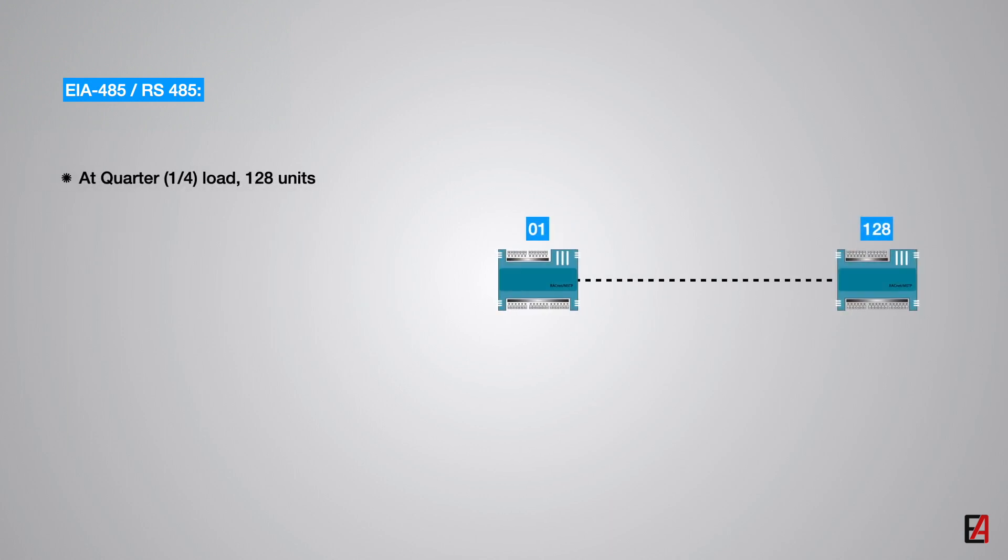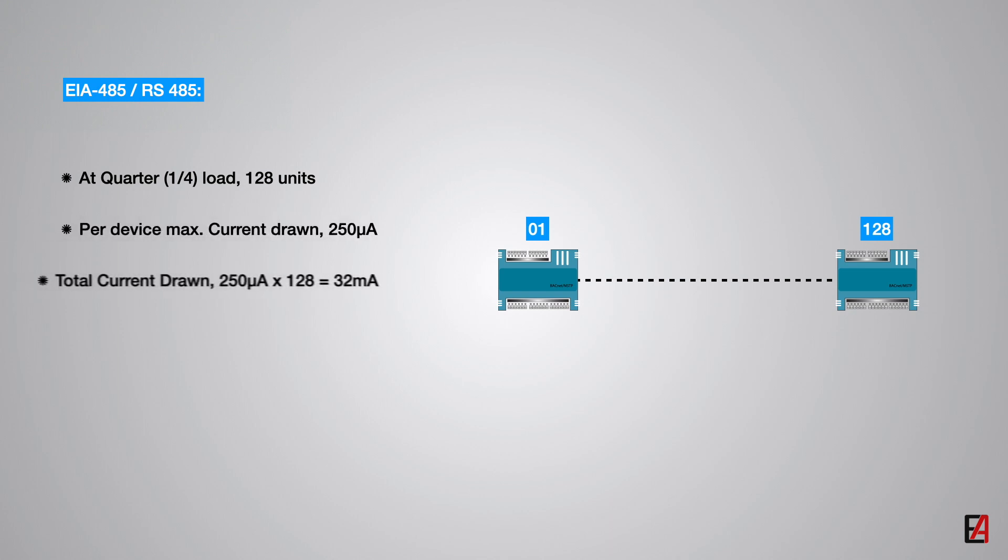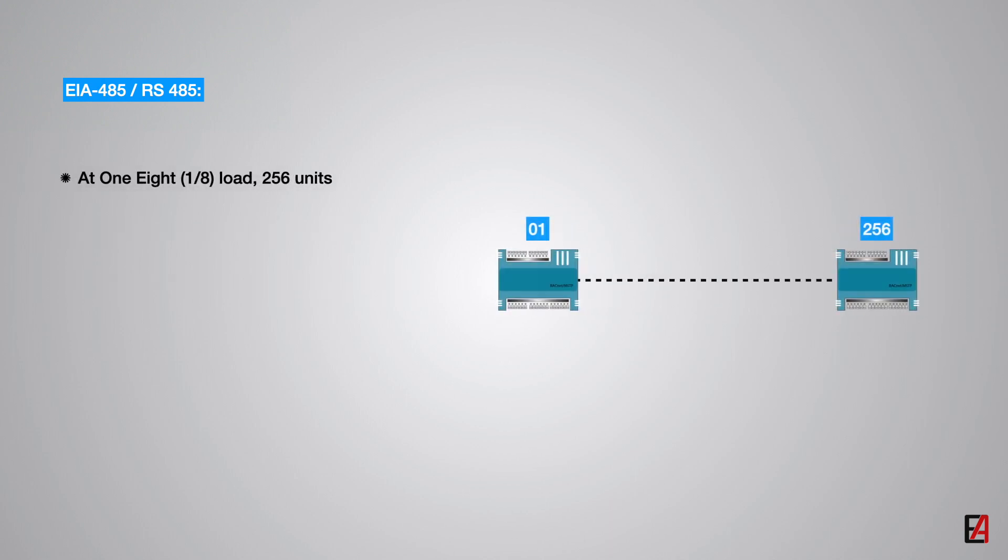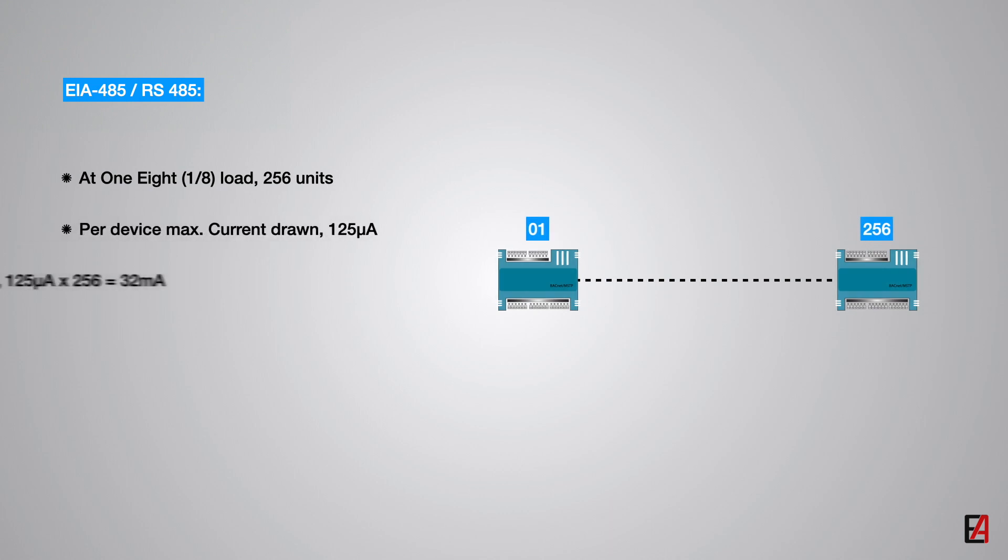At quarter load, 128 units can be connected on a single MSTP network with per device maximum current drawn less than or equal to 250 µA. Finally, at one-eighth of the load, a maximum of 256 devices can be connected on a single network with per device drawing current not more than 125 µA to comply with the RS-485 standard.